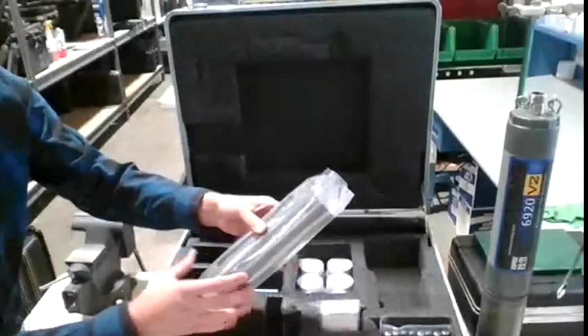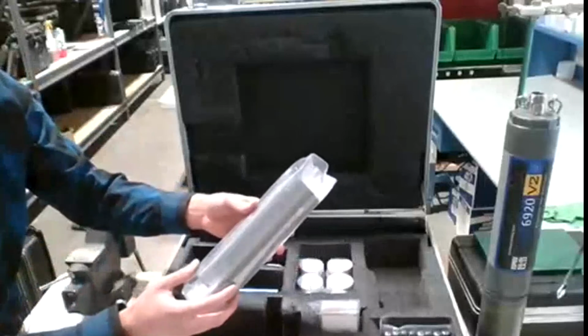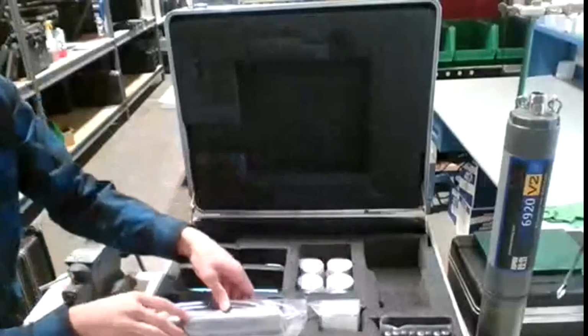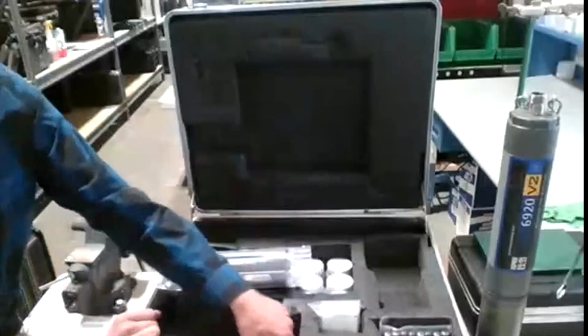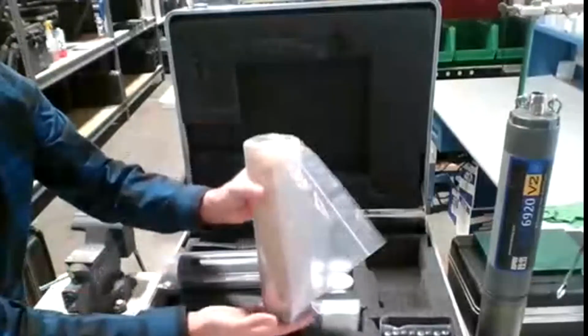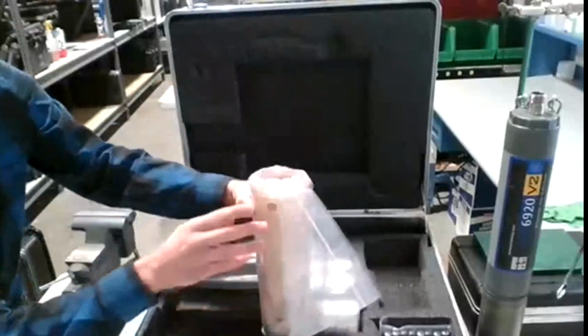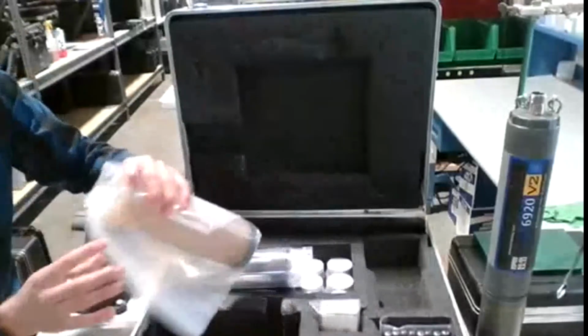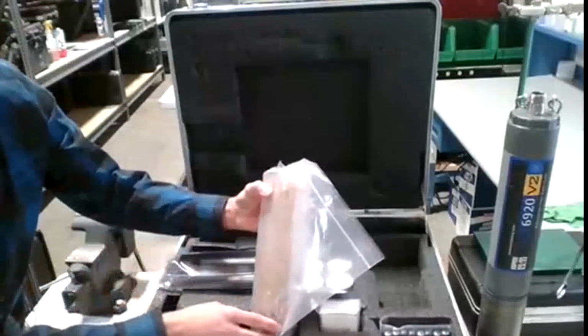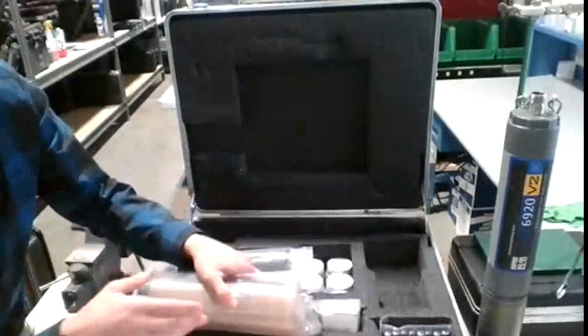Here we have a probe guard. So for both in situ and long-term monitoring, sorry, you are going to want the probe guard to protect the sensors. And then lastly, if you are just doing low flow sampling, which also is discrete sampling, we have a low flow chamber, which you'll install the top of the 6920 in here. You'll have 2 barbed ports that are also provided. They're actually just inside the flow cell right now. And then you can hook that up to either a peri pump or any type of pump that you have to get that low flow sample.